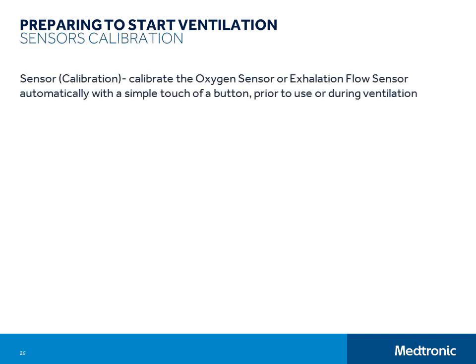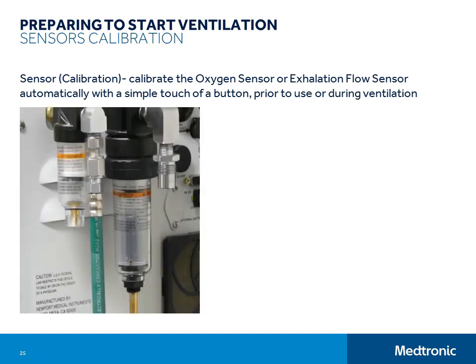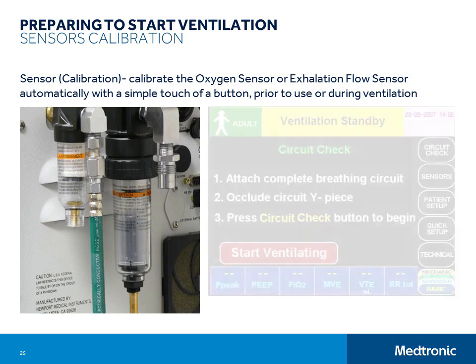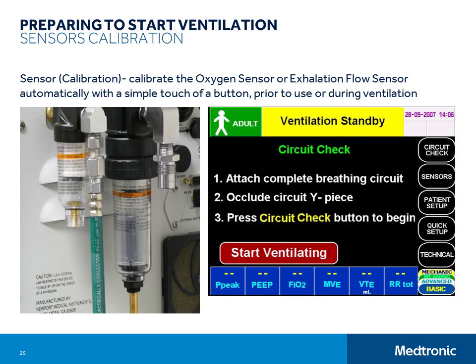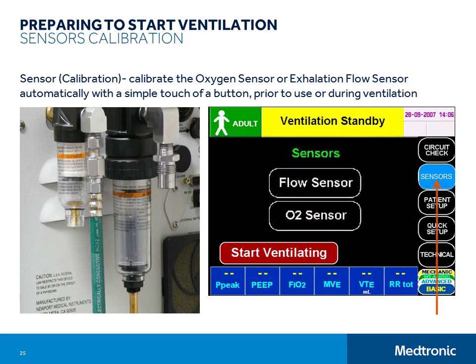The next step is sensor calibration. You must have oxygen connected to the ventilator in order to perform the oxygen sensor calibration. Low flow and zero offset flow sensor calibrations are both performed during the circuit check. So if you have already performed and passed a circuit check, you don't need to do a flow sensor cal during setup, only an oxygen sensor cal. Just touch the Sensors menu button, then touch the O2 sensor button to initiate the calibration. The sensor is also calibrated anytime the O2 3-minute button is pressed.